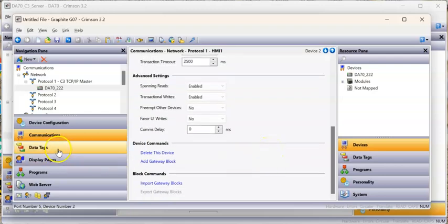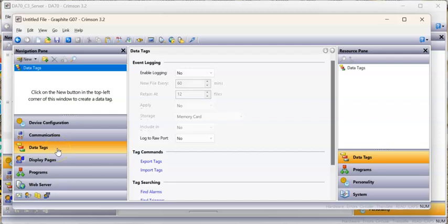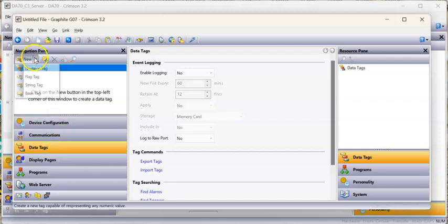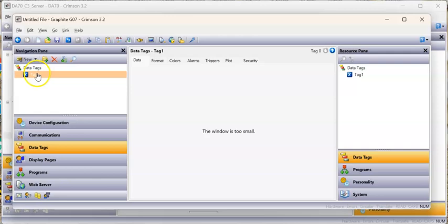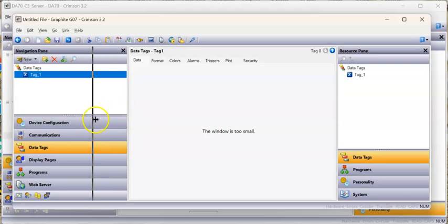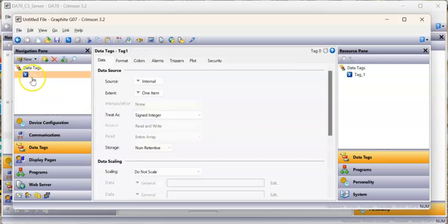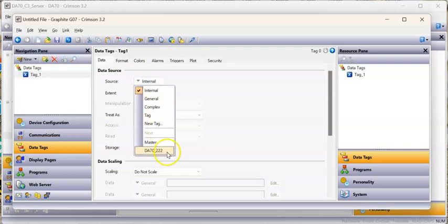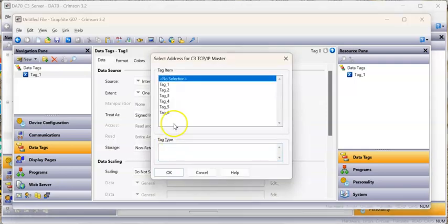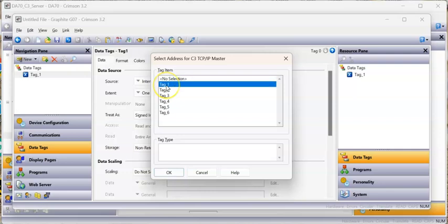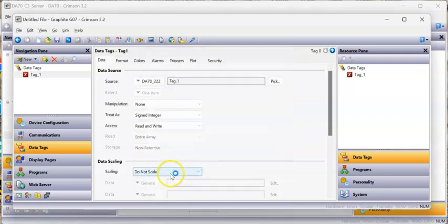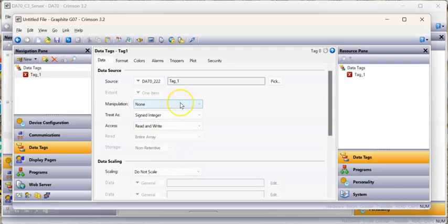Now I'm going to go over here to data tags and create a couple of tags. I'll do a numeric tag and call this tag_one. Notice it's blue because it's internal, it's not mapped to anything. If I go here to the internal pull-down, I can go down to that DA70 device, that's the one I just created. Click on that and look, here's the tag names. Now I can click here and set that up. And now that's going to talk to the DA70 as a server and go to town with my graphite HMI.